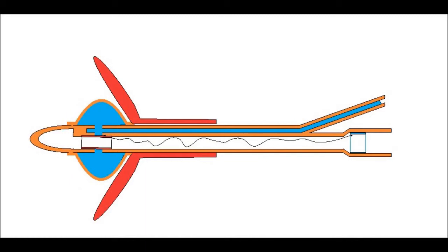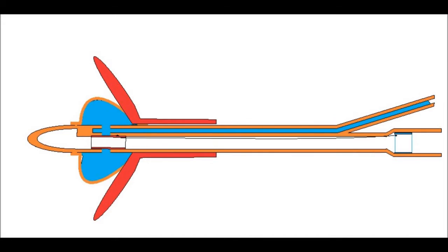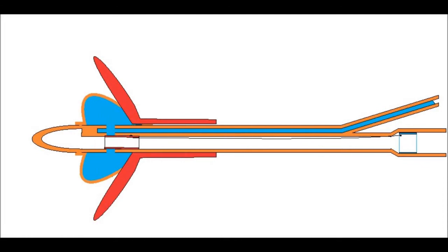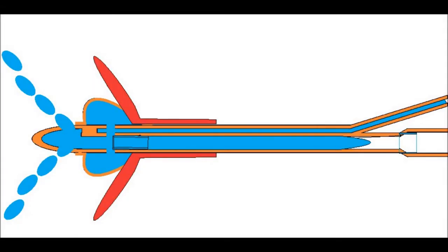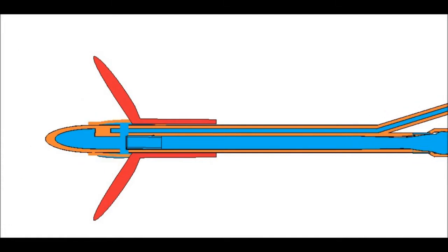In the event the catheter is pulled backwards by the patient or snagged and pulled backwards, the distance between the anchor and the stretch valve increases and the filament becomes taut. At a certain point, the stretch valve is moved to the right, which opens the drainage channels and allows fluid to drain from the balloon. Without the balloon inflated, the catheter is easily withdrawn from the bladder and urethra with no damage to the urethra.